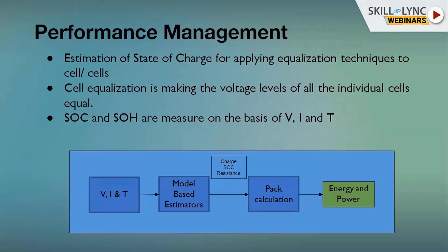The most important part of the BMS is performance management. The BMS is responsible for estimating SOC and applying equalization techniques to cells, making the voltage levels of individual cells equal. The main requirement is to keep all series-connected cells in an equalized state with equal voltages, maintaining them in a safe operating state. SOC and SOH measurements are performed by the BMS algorithm, calculated on the basis of voltage, current, and temperature read from the battery monitoring units.